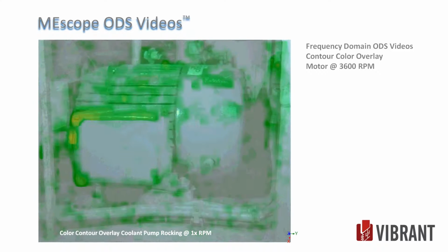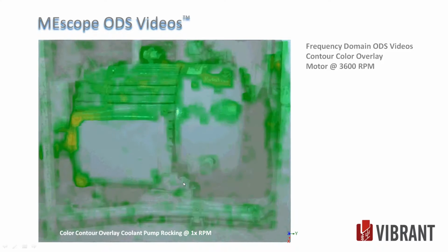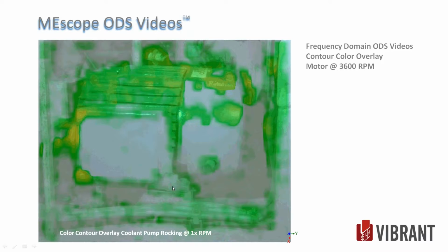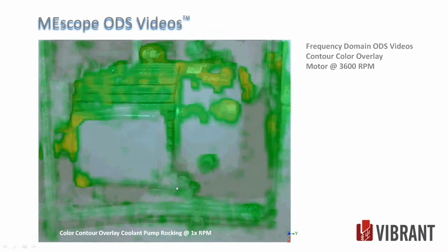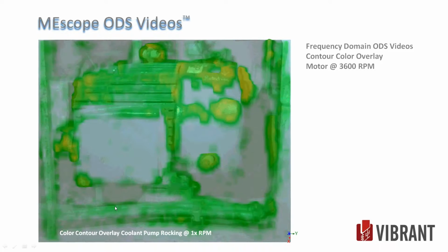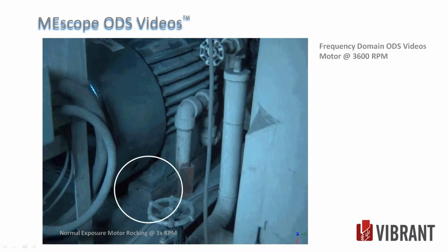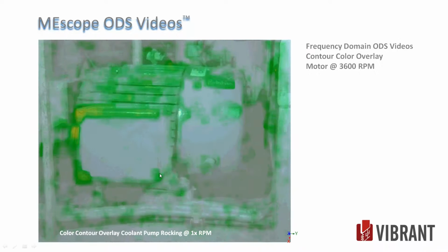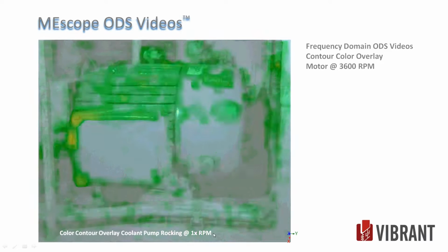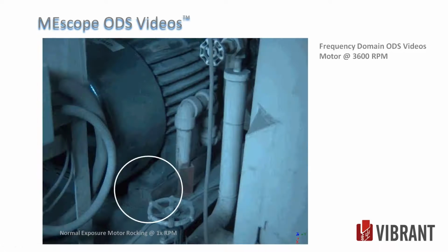We put some color contour on it, and we can see some motion here in the foundation and the foot, but it doesn't look like relative motion. We're going to need a better shot of that to see what's going on. This was my best shot view at the other side. So here it was open. I could put my camera in line with it and see fairly good this foot, what's going on. But it looked like it was moving in phase with each other.